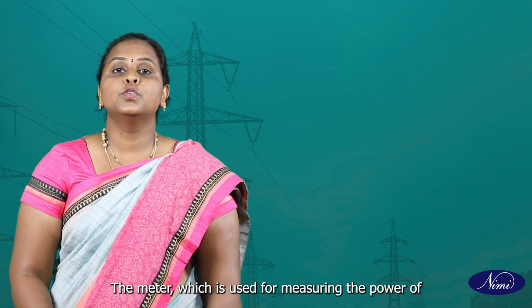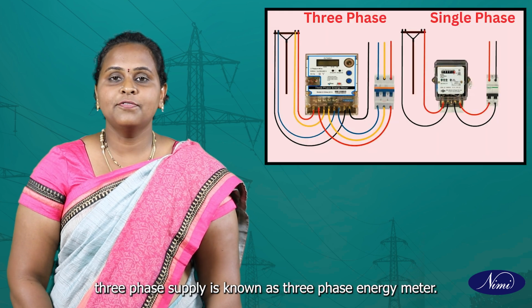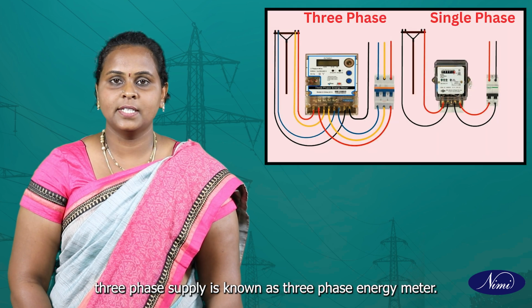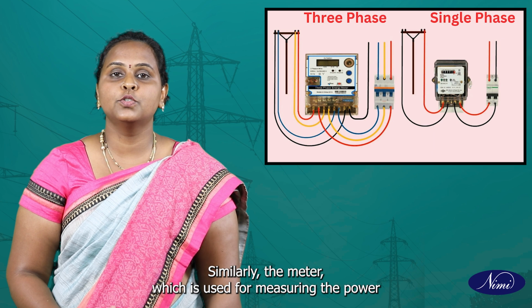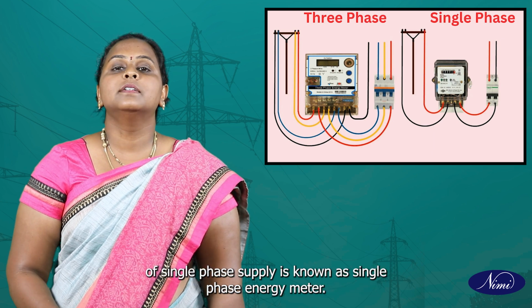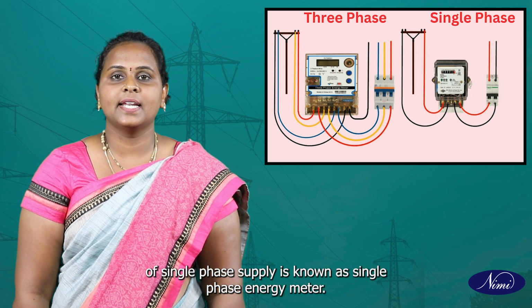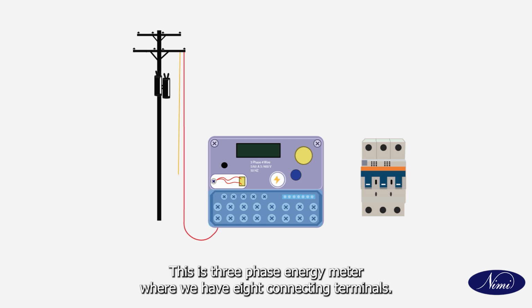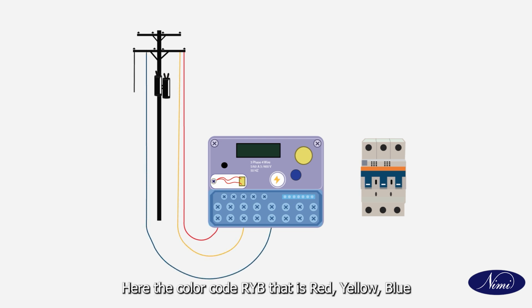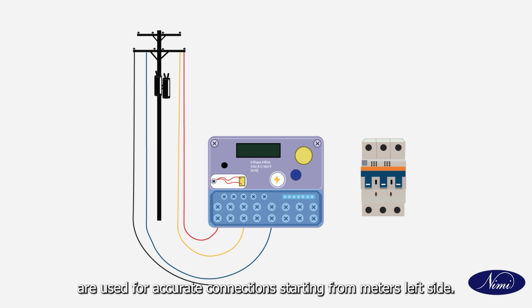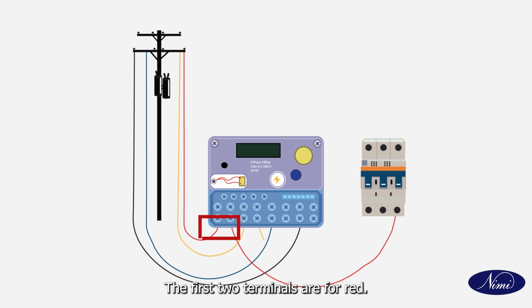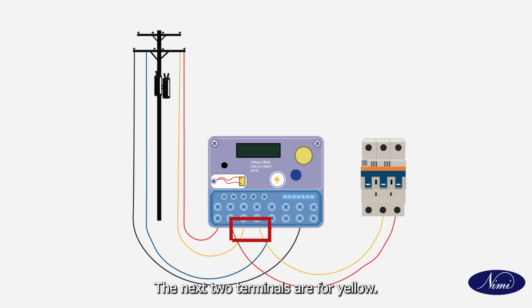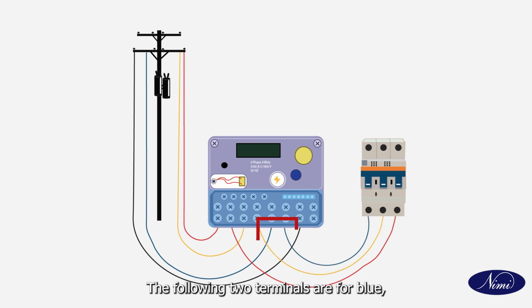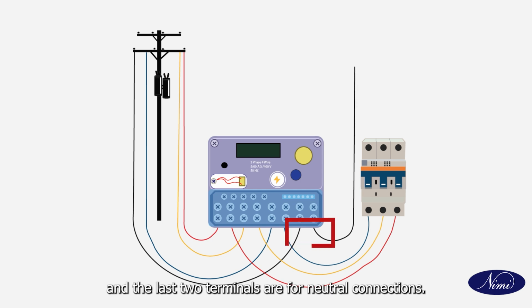The meter which is used for measuring the power of 3-phase supply is known as 3-phase energy meter. Similarly, the meter which is used for measuring the power of single phase supply is known as single phase energy meter. This is 3-phase energy meter where we have 8 connecting terminals. Here the color code RYB, that is red, yellow, blue, are used for accurate connections. Starting from meter's left side, the first 2 terminals are for red, the next 2 terminals are for yellow, the following 2 terminals are for blue, and the last 2 terminals are for neutral connections.